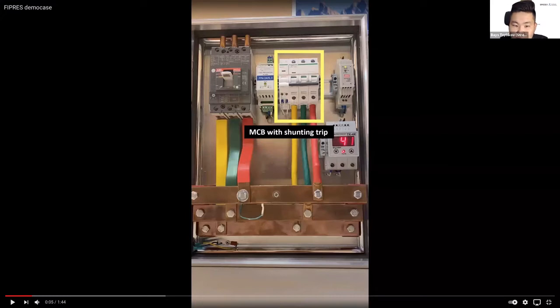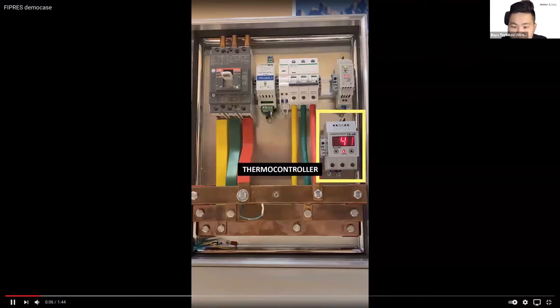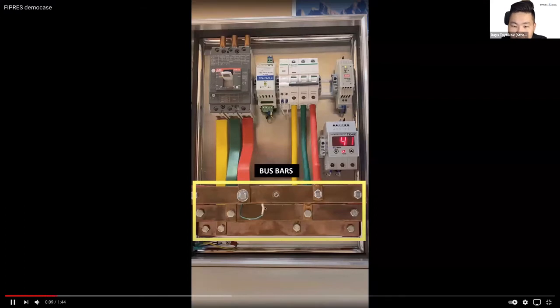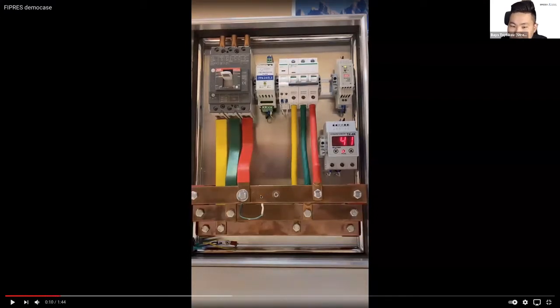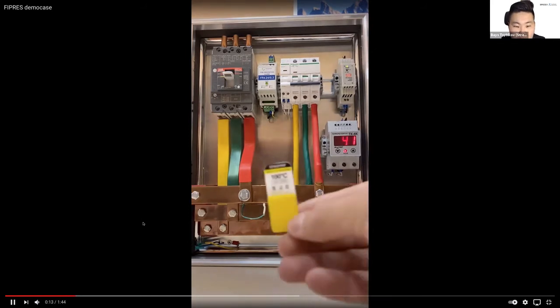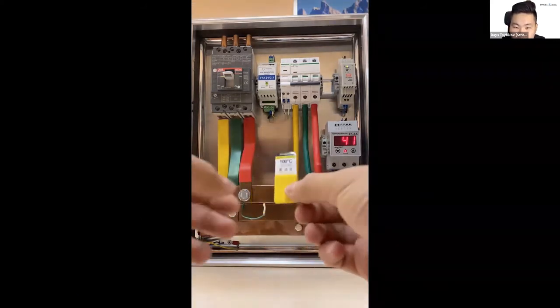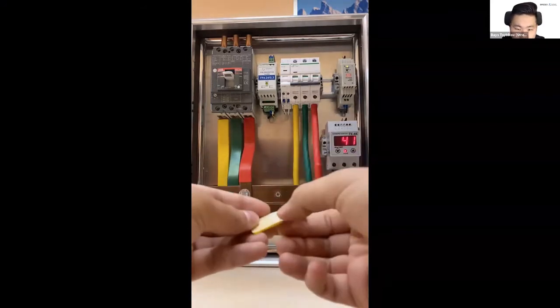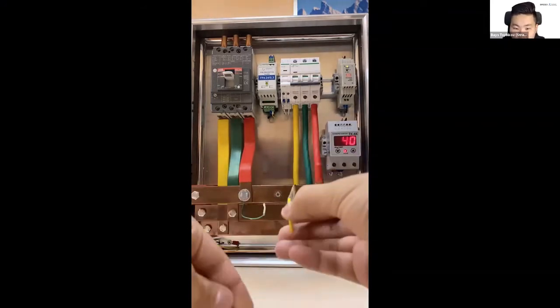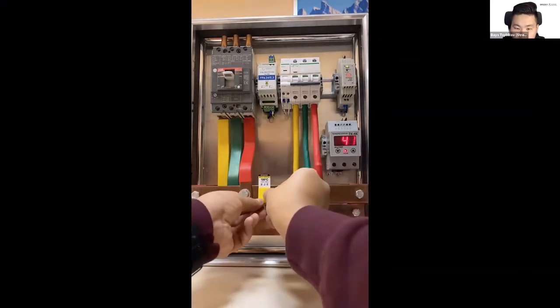In this demonstration case, we have here MCBs, a thermal controller, and the bus bars. Behind these bus bars, there is a heater, and the temperature of this point is shown here. This is the FPA, and the dry contact output of FPA is connected to the shunting trip device. So what you need to do? This is the RFPT, the smallest sticker in our range. It's used for small volumes like 100 liters. So we need to just simply glue the sticker to a bus bar.